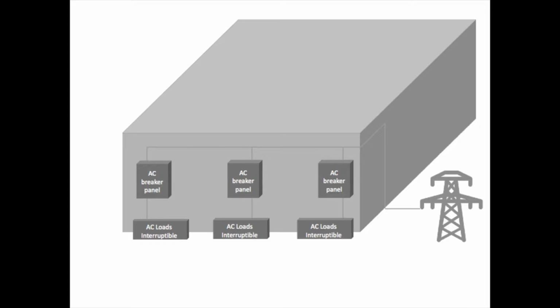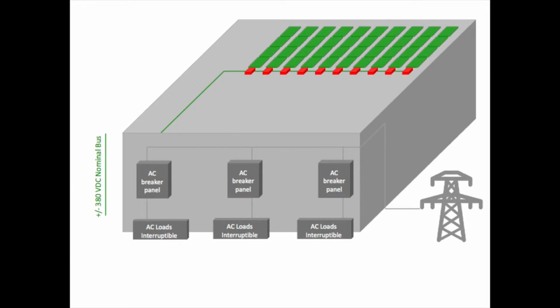First, local generation sources and storage, if they don't already exist, are installed on site. A common anchor for a building microgrid is a rooftop solar plant, shown in green, to provide peak energy. While intermittent, solar generation typically peaks in parallel with consumption on hot, sunny days, reducing energy requirements and capacity charges. The PV plant is connected to the microgrid using low-cost DC-DC converters, shown in red, for instance a solar optimizer, via a common DC bus.